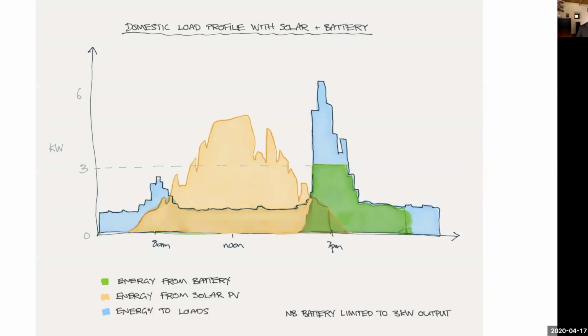And it can be the kilowatt hour demand. That's one part of it, the load energy that you need to produce enough renewables over a day or even a bad day, or a bad month. But it's also the peak demand. How high are those peaks? Well, the coincidental peaks. I've crudely drawn this chart here, but when you look at real load data, it's very digital. Things just turn on and off. Your toaster doesn't slowly ramp up in power. It comes on at 1500 watts, it turns off at 0. It doesn't ramp up slowly.